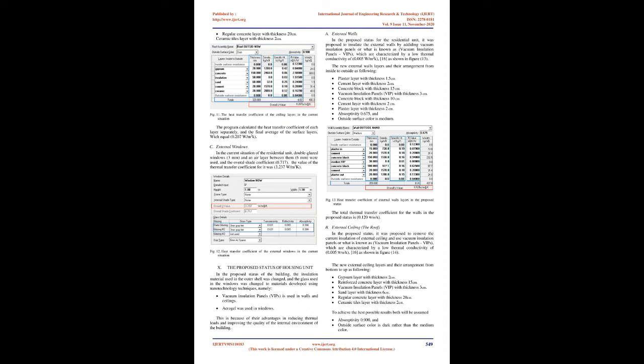Ameliorating the building energy performance. The following characteristics need to be assessed. Heat transfer coefficient, U, W/m2K. Heat transfer coefficient, or thermal transmittance, is the sum of the resistances, Rc, for each building material, the external surface resistance, Rso, and the envelope interfaces. The R value, m2K/W, is the material thermal resistance, calculated from the relation R equals t over lambda, m2K/W, where t is the material thickness in meters and lambda is the thermal conductivity of the material.